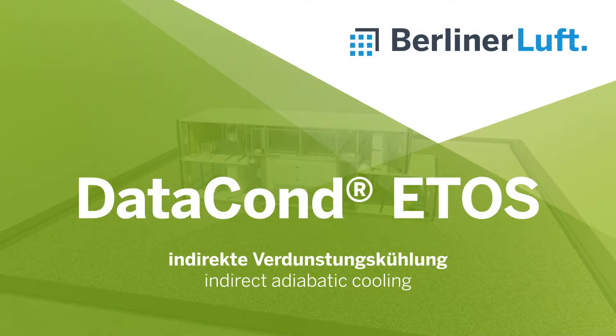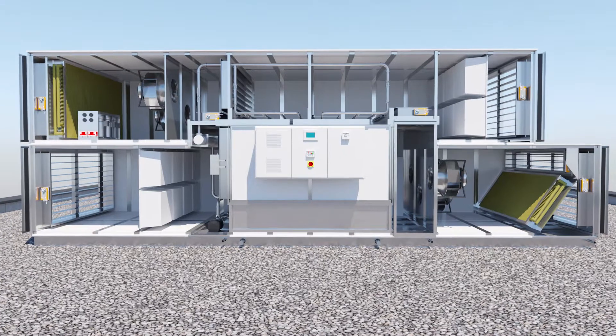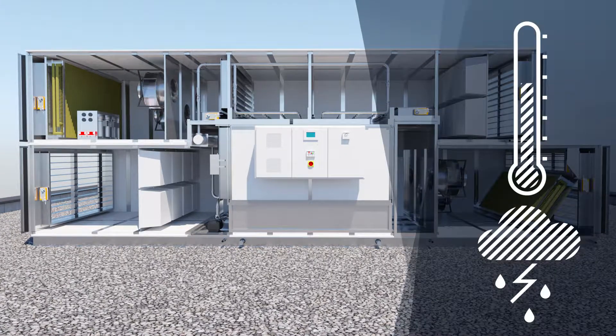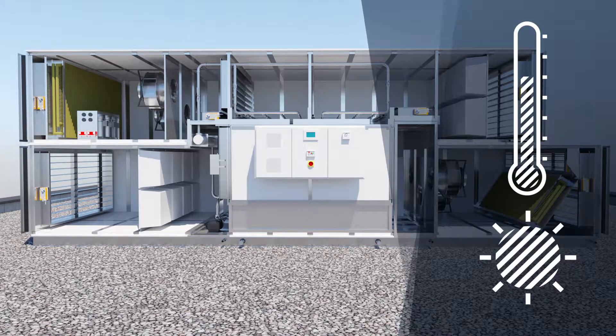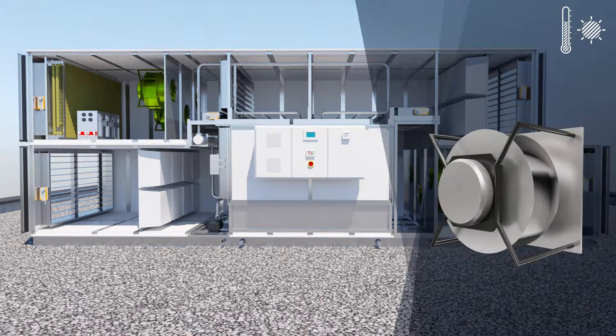In summertime temperatures, DATACOND ETOS starts indirect evaporative cooling and cools the supply air temperature to within 1.5K of the wet bulb temperature of the outdoor air. In this mode, the exhaust air fans speed up.